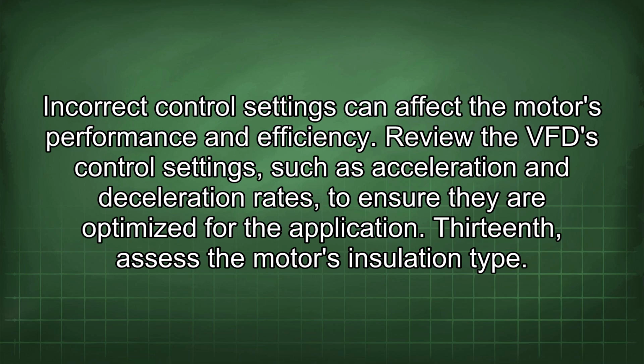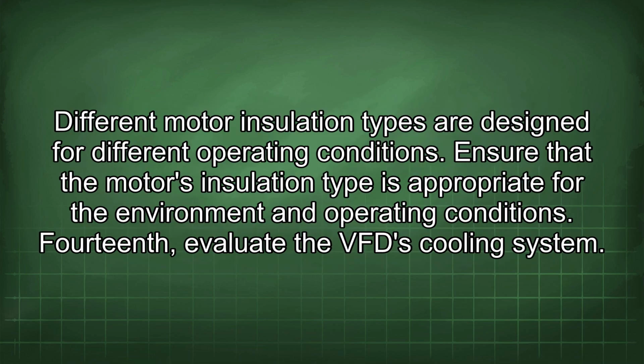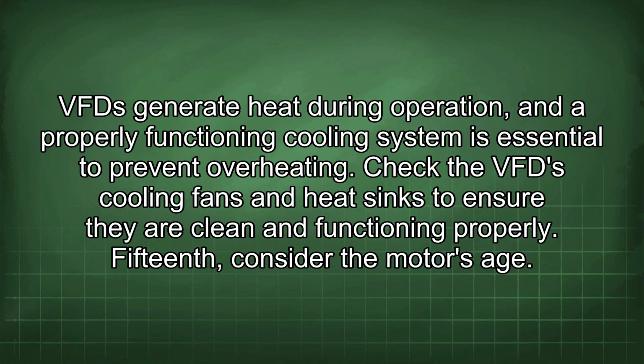13th, assess the motor's insulation type. Different motor insulation types are designed for different operating conditions. Ensure that the motor's insulation type is appropriate for the environment and operating conditions. 14th, evaluate the VFD cooling system. VFD generate heat during operation, and a properly functioning cooling system is essential to prevent overheating. Check the VFD cooling fans and heat sinks to ensure they are clean and functioning properly.